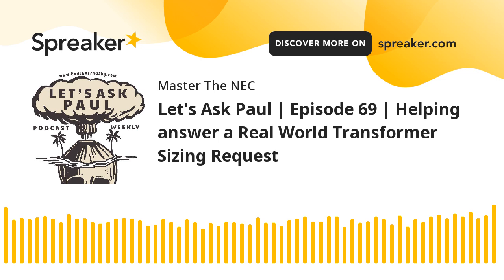What is the overcurrent protective device rating for a 480 volt main? And I think I gave you that. It looks to me like it would be a 45 or a 70, depending on whether you're doing a 30 kVA or a 45 kVA, your choice. Whether you want that additional capacity, whether you're installing a panel, maybe trying to get other loads out of it, like for that receptacle within 25 feet or whatever. So you've got that option.